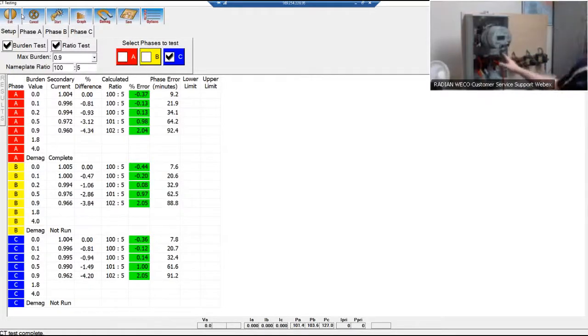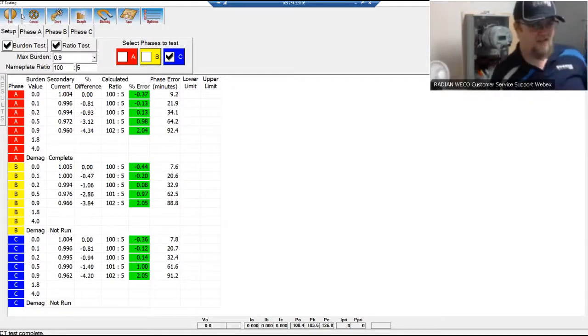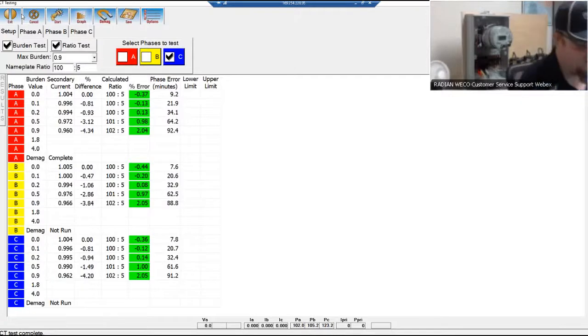And then once I was done, I can then pull all those off as well. Sort that out, pull out my duckbill, that's moving the whole thing. Close up my switch. Remove all of my stuff here, unclip from the test switch. Make sure everything's closed. I'm good to go. So that kind of covers over everything CT-wise, testing-wise for the RW and the Bantam Plus. So I'm going to shift over here real quick.